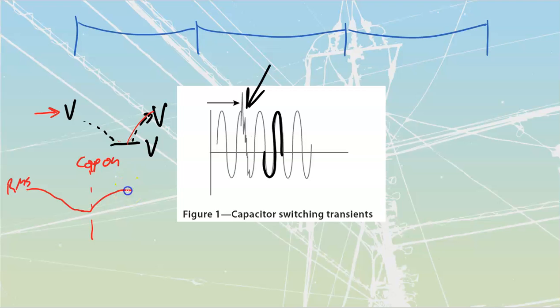The cap comes on and brings the voltage up a little higher. There's a certain amount of timing before BC Hydro's transformer regulator changes taps, since that's a mechanical process and we don't want a lot of mechanical opening and closing.